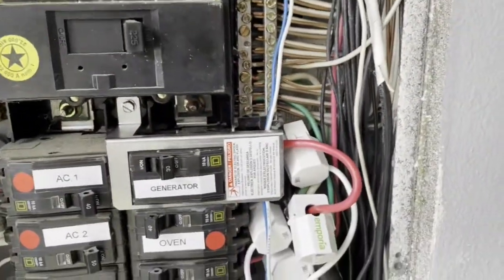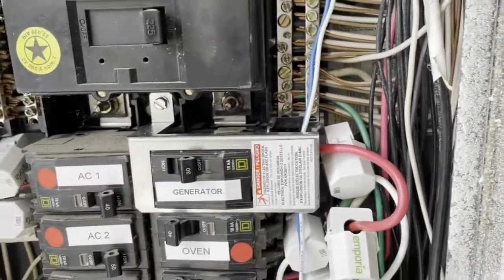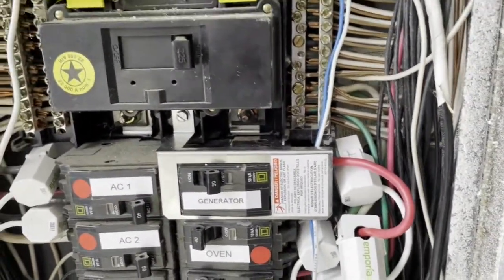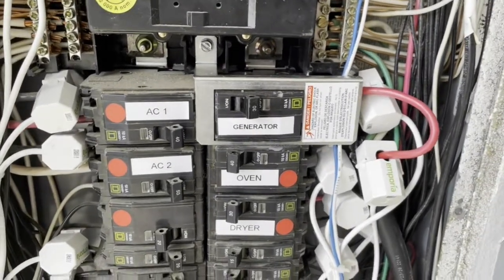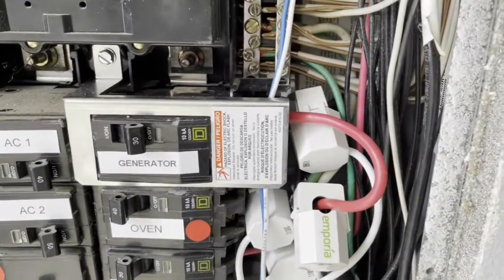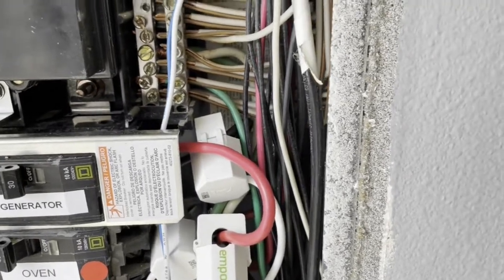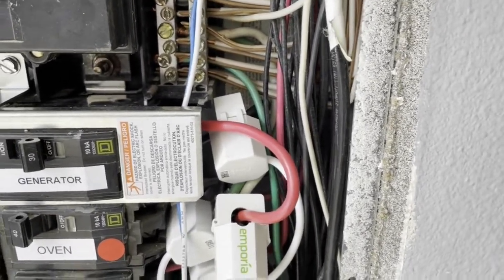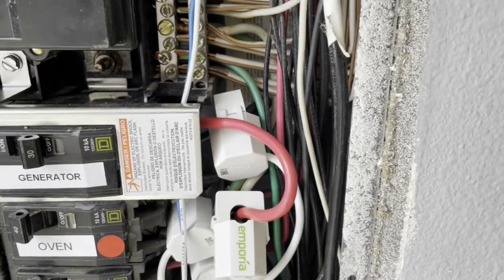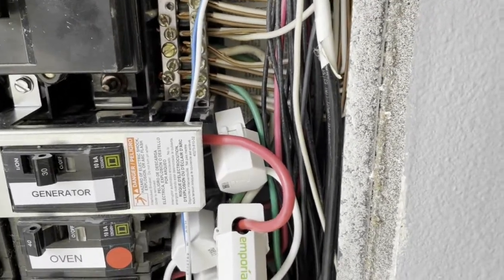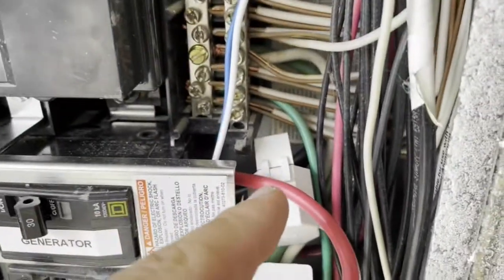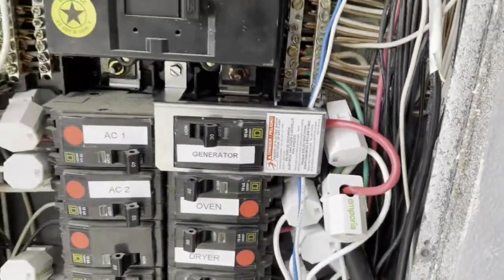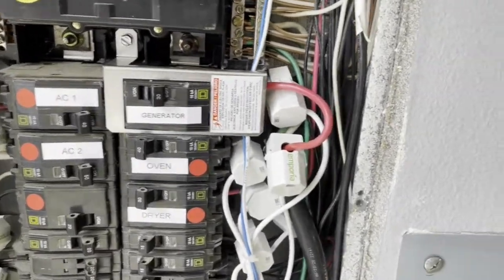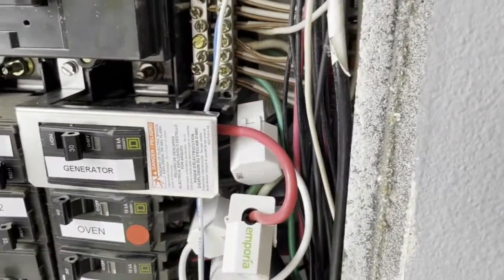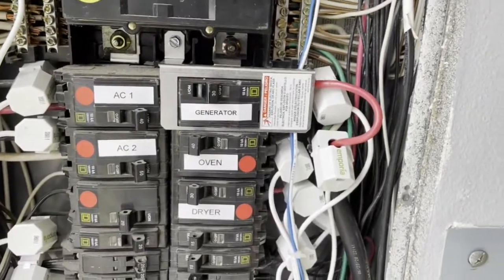Coming to the generator, the story changes, because the generator will never be balanced—some loads in your house are 240 and some are 120. That means one phase will always draw more or less current than the other. So you need to monitor both phases. That's why I put 2 clamps, one on red and one on black, and the app has a great feature that recognizes these sensors as a generator or solar power.